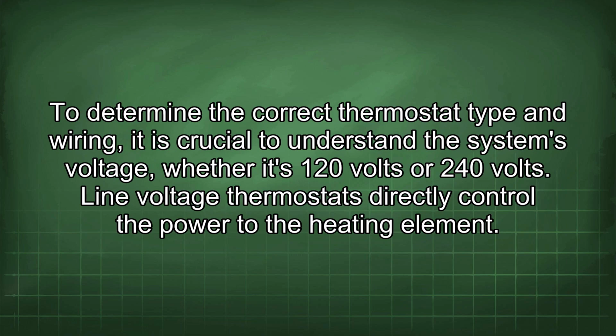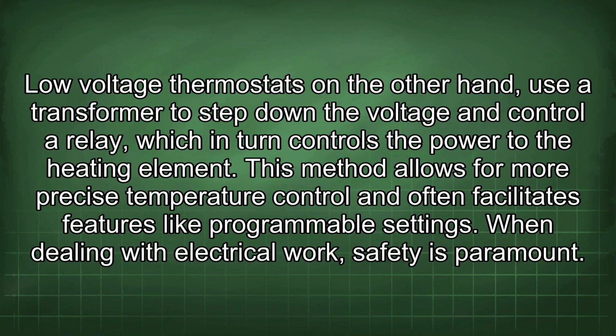To determine the correct thermostat type and wiring, it is crucial to understand the system's voltage, whether it's 120 volts or 240 volts. Line voltage thermostats directly control the power to the heating element. Low voltage thermostats, on the other hand, use a transformer to step down the voltage and control a relay, which in turn controls the power to the heating element. This method allows for more precise temperature control and often facilitates features like programmable settings.